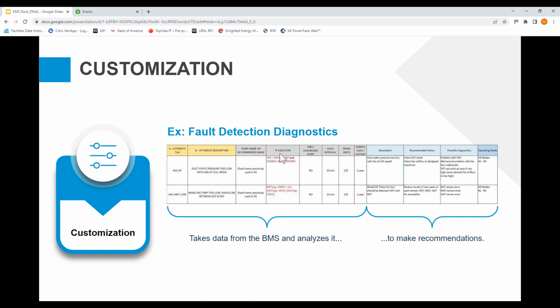Well, this is kind of the same thing. It's a bit more manual, and I'd say the distinction is that we're seeing a lot of fault detection diagnostics actually be implemented even at the BMS level, beyond just at your energy management system. In fact, it's also becoming a requirement, at least in the state of California, as a code requirement. It's already one for package units, and I can see it kind of expanding out from there.